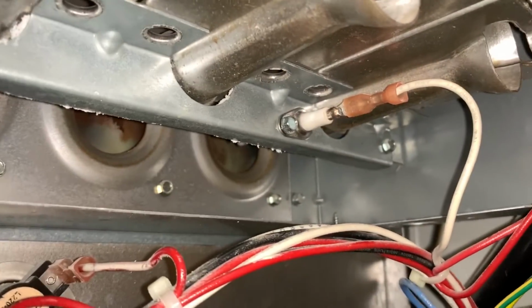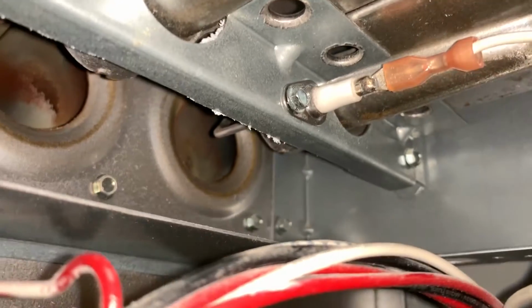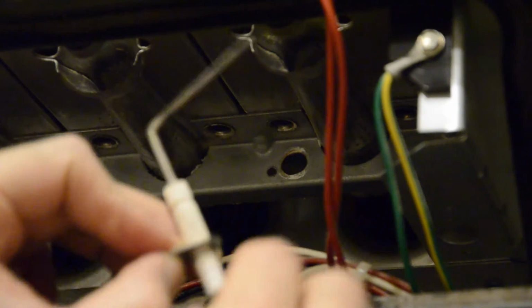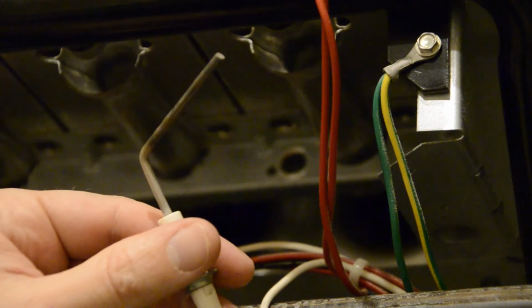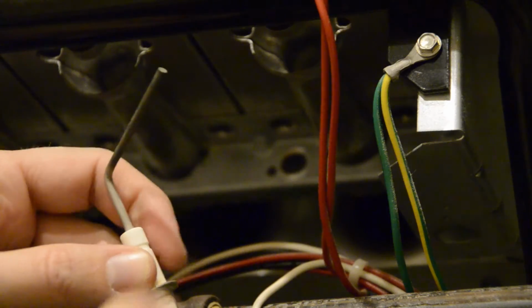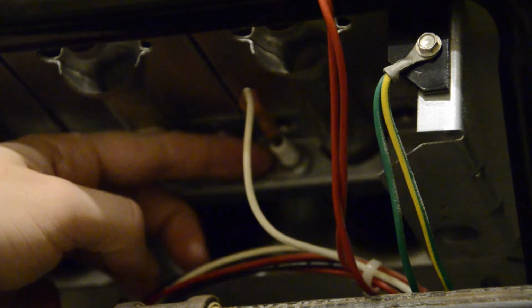We will then remove and inspect the flame sensor located here. Remove the screw holding the sensor in. To remove the carbon buildup, use a dollar bill and lightly sand it down. Do not use any sandpaper or anything with aggressive grit, as it may ruin the sensor. With the sensor clean, mount it back into place and tighten down the screw holding it.